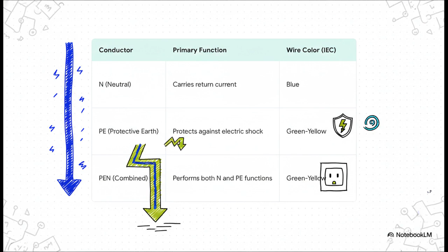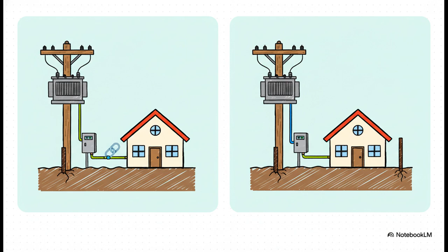Now for section 4, where we put it all together to form the words. Let's meet the 3 main systems you'll actually find out there in the world: TN, TT, and IT. So let's put the 2 most common ones side by side. In a TN system, your safety connection is one continuous wire that goes all the way back to the transformer's earthing point. But in a TT system, your building has its own private earth connection, literally like a metal rod driven into the ground that's totally independent from the source.